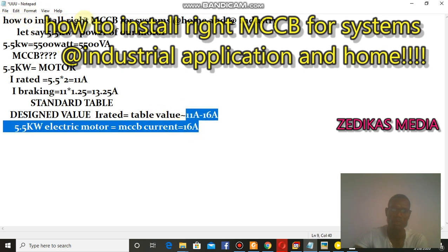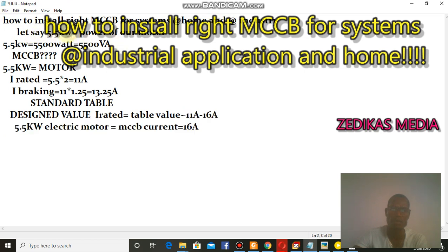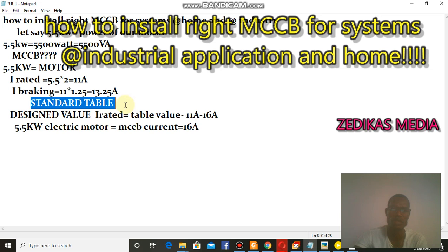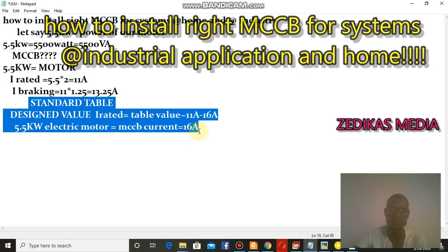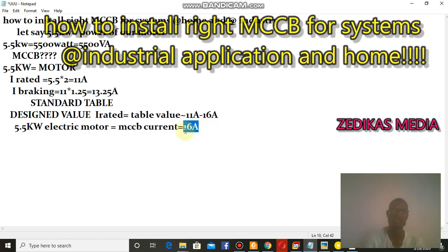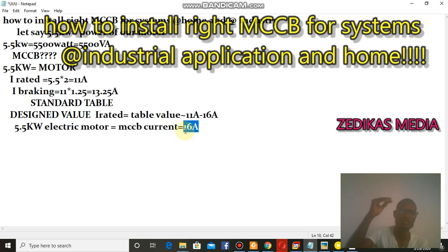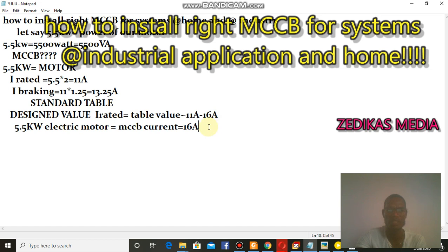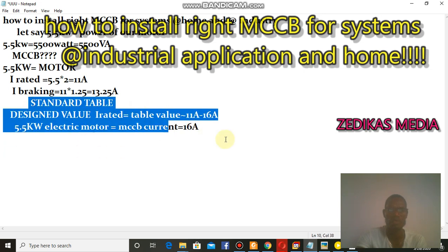Basically, this is how to install the right MCCB system for home or industry. For our 5.5 kilowatt motor, we select a 16 ampere motor breaker controller to protect the plant from damage or overload problems. If the current exceeds 16 ampere — say it reaches 18 or 20 ampere — the motor will trip. This ampere rating defines the tripping threshold for our system.